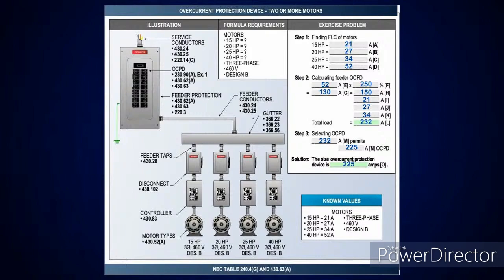I think they did this. Okay. But in this case, we got 4 motors. They're all 3-phase, 460 volt design B. I've got a 15, 20, 25, and 40 horsepower motor. You go over to table 430.250. You pick up your 460 volt, come down, pick up your 15 horsepower. Tells you it's good for 21 amps. The 20 horsepower is good for 27. Your 25 horsepower is good for 34 amps. And your 40 horsepower is good for 52 amps.